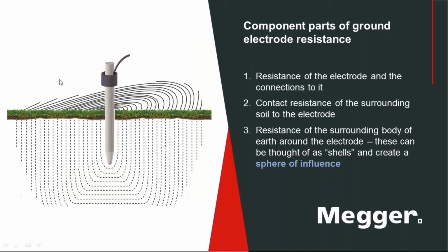We show what we call spheres of influence. In other words, the further you get away, the critical thing to remember is this is not like the gauge of a wire that stays the same. This gets bigger and bigger as you go further away. So consequently, law of diminishing returns, eventually it becomes zero. At some point, you're so far away that any additional soil is not contributing anything significant. So it's the soil that's impacted around your electrode that's important, and that's what you're going to want to measure.